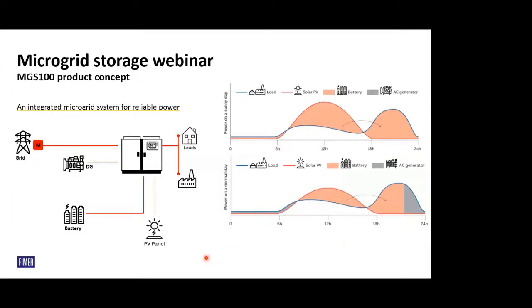Going to the product concept, as we said, a microgrid is usually like a black box. How it usually works is, let's imagine a village which had no power. Now we go and install a PV plant and a diesel generator for backup power. You see the generation usually happens this way, with the peak over 300 days in a year. And this will be the typical load curve, where at night time it is usually residential loads, and the load increases. What you store in excess will be used in the evening time.